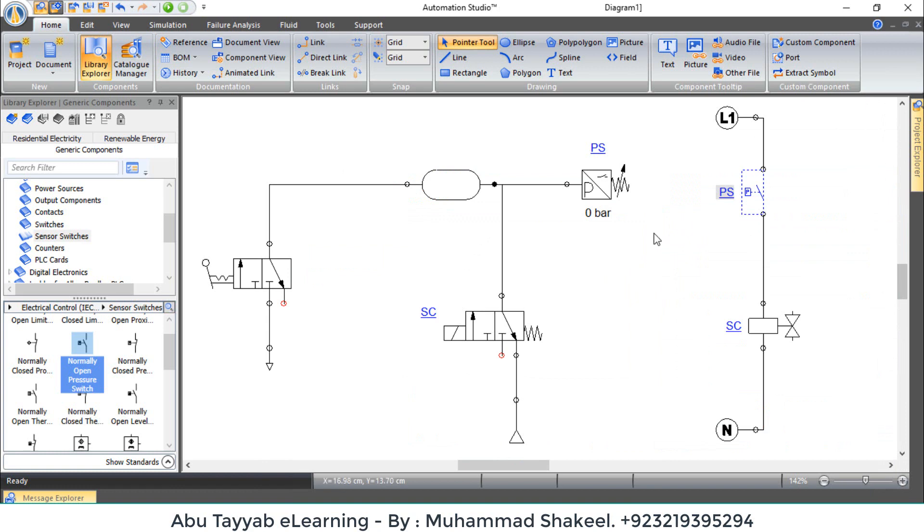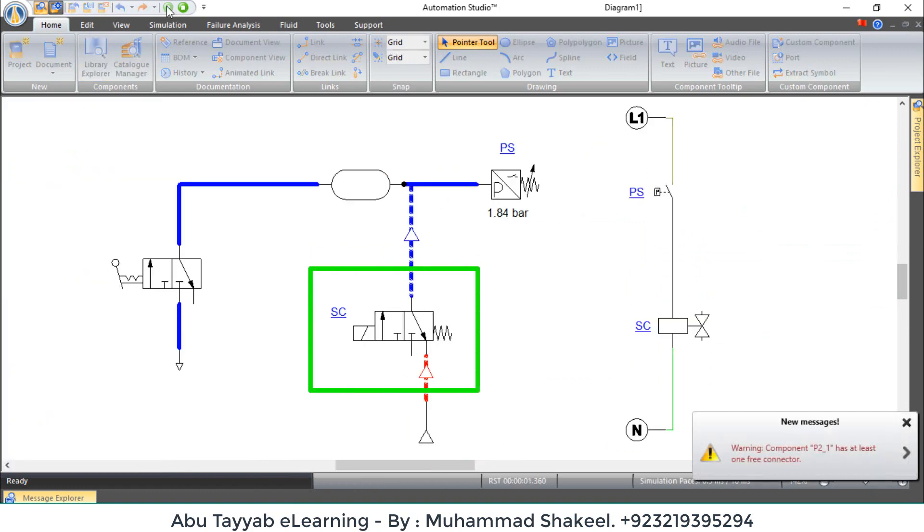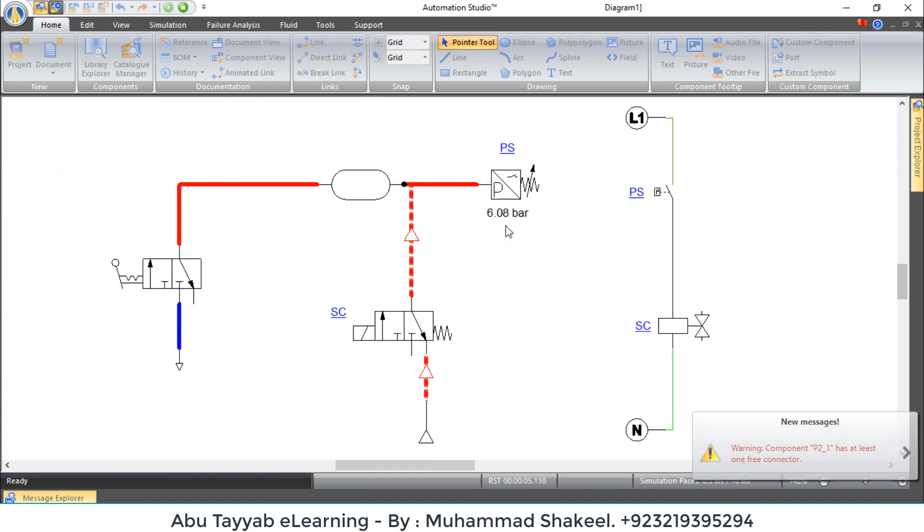This valve is open and pressure is increasing in accumulator. When pressure goes to 8 bar, the pressure switch contact closed and solenoid coil operated, and the valve will be closed automatically.